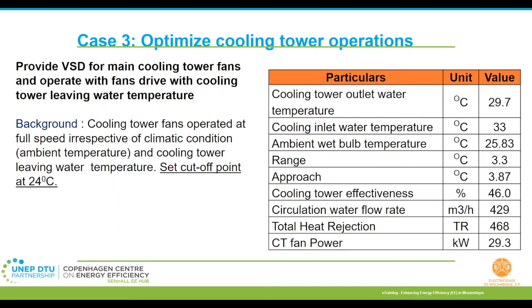Now, the job of the cooling tower is to take the cooling water, the hot water that comes from the chillers or the other process areas. It rejects that heat into the atmosphere, cools down the water, and then sends it back to the user end requirements. So the set point was fixed at 24 degrees. That means if the cooling water temperature from the cooling tower reduces to 24 degrees, then the cooling tower fans would turn off. And when the temperature increases, the fans would turn on again.